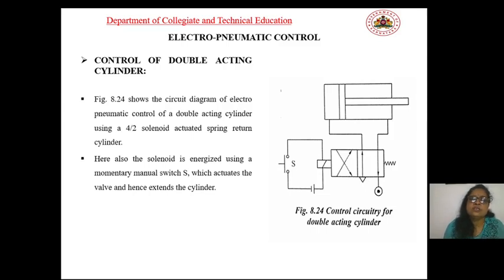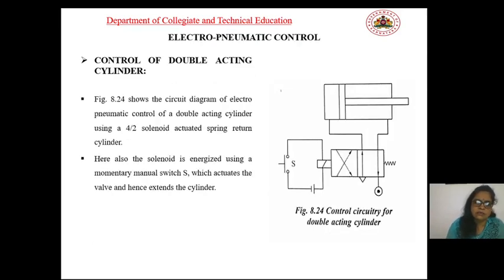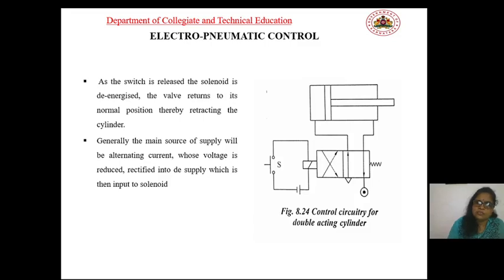The figure shows the circuit diagram of electro-pneumatic control of a double-acting cylinder. In the double-acting cylinder, the electro-pneumatic control uses a 4/2 solenoid-actuated spring-return valve. The solenoid is energized using a momentary manual switch S, which activates the valve and extends the cylinder. As the switch is released, the solenoid is de-energized, the valve returns to its original position, thereby retracting the cylinder. The main AC supply is rectified into DC supply, which is input to the solenoid.